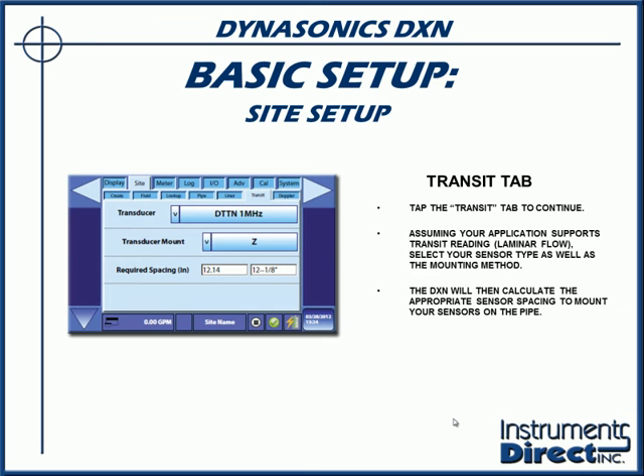You'd select your type of transducer mounting, and then on the bottom of that, this is the key, it will give you the required transducer spacing, the differential between the transit time transducers. As you saw, the man in the rowboat and the reflection off the back wall of the different configurations, they all had to have a specific trajectory, and you needed to know specifically where the pipe transducers needed to be mounted to receive and transmit those signals. The previous data you put in basically calculated out that information of all the different sound speeds.